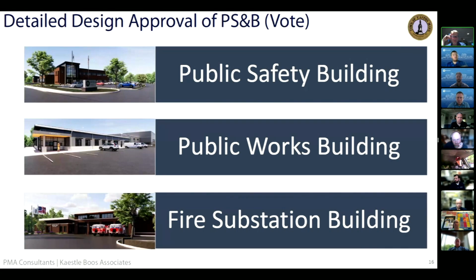The other spaces, the bays, are they doing just radiant? Yeah, right now the bays are heated with radiant and some supplemental, I think they're like Modine units, so hydronic heated water units, to basically make up when the overhead doors open in the winter and there's a big gush of cold air. Those Modine units are there to temper the space and do freeze prevention for the fire protection system. So that's just strictly heating in the bays.